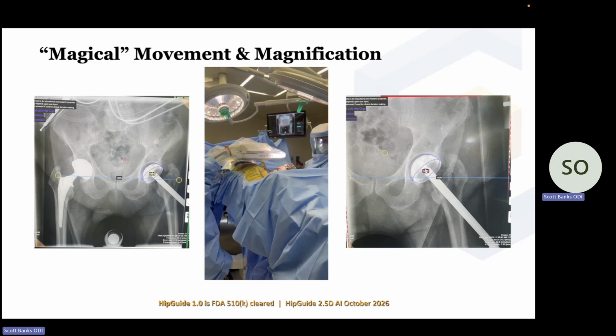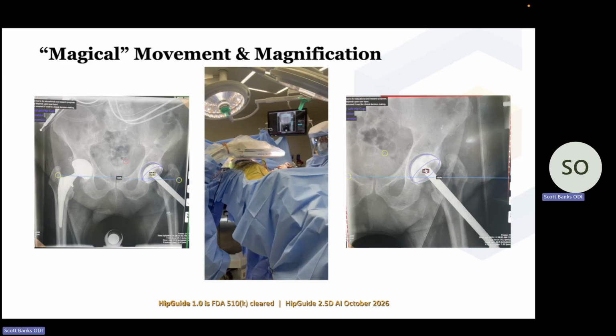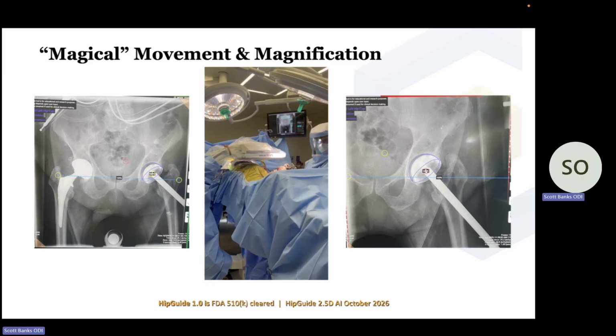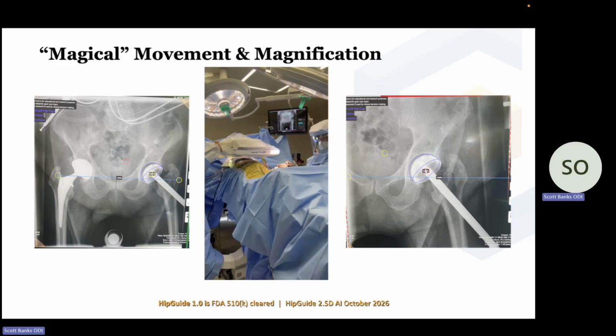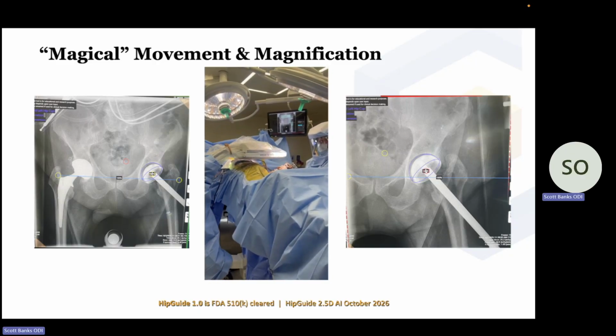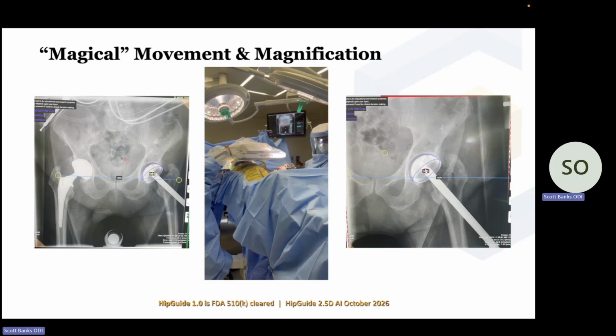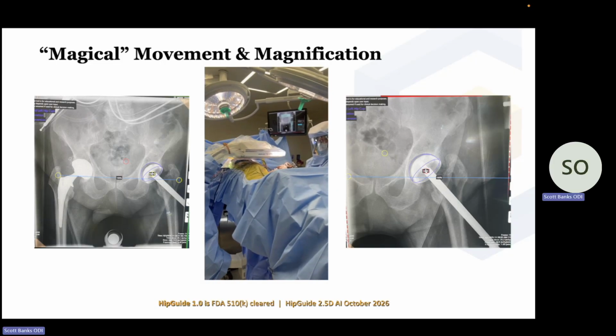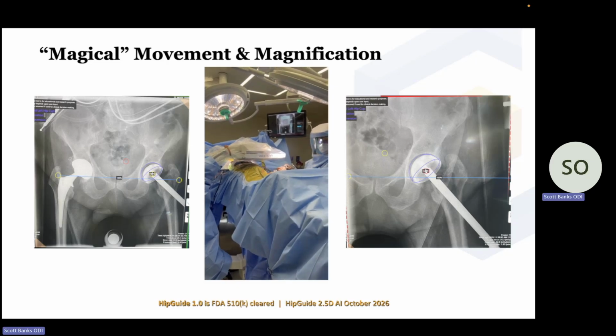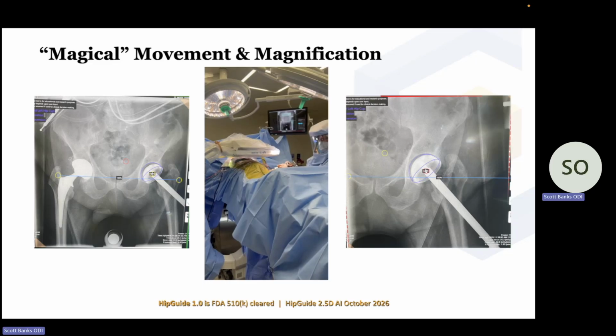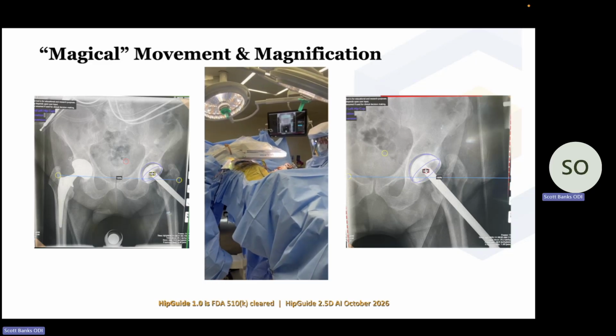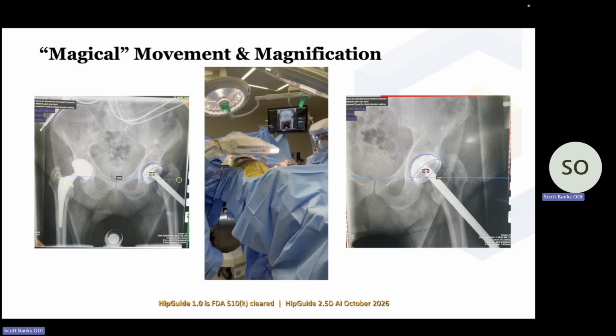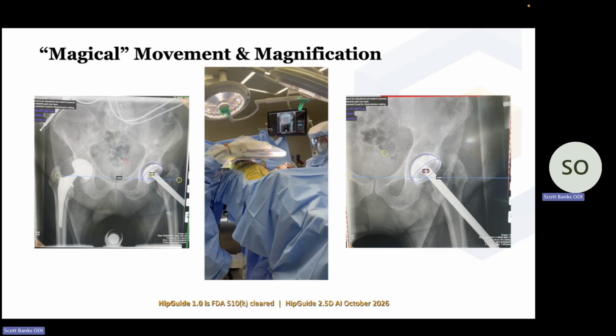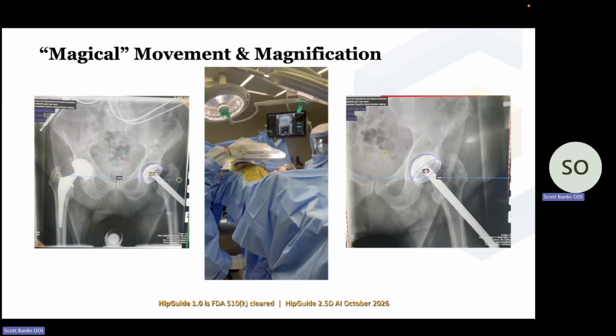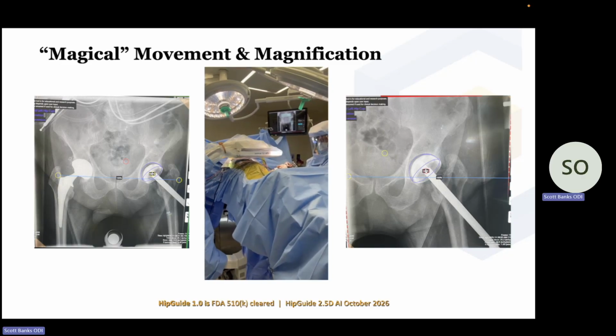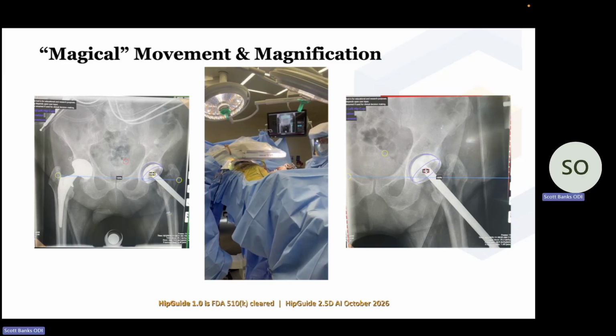So we, with our machines, know exactly and calibrate where the center of projection is. So when we project, for example, an acetabular component onto that screen, and we say that we want it, for example, at 40 degrees of inclination and 20 degrees of anteversion relative to that projection, we can show the correct projection regardless of where that component is in the screen. It can be in any corner or the center of our 17 by 17 inch fluoroscopic detector, and we will accurately show those angles for that positioning within the image.